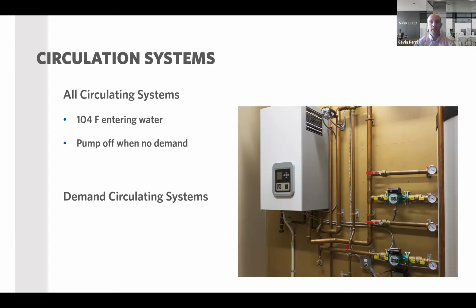And this is something that I don't see typically when I'm out in the field. Usually these little recirculation pumps like you see on the screen here are running 24/7, constantly and just nonstop. So what this means is that controls is now going to be needed to program and monitor these domestic water pumps and loops in the new code cycle.